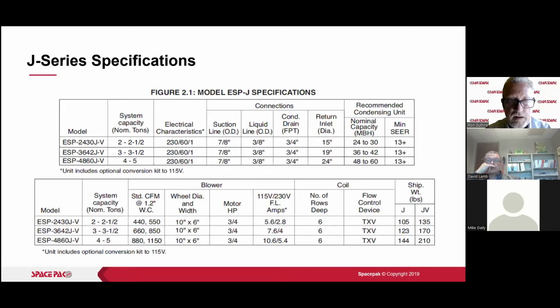And one of the aspects that we need to look at is that if we're doing a commercial job at 208, which is predominantly where you would find 208 volts, the board is looking for 230 volts, and it has some leeway in there. But at 208 volts, it sees that as low voltage, and goofy things start happening with the control of the unit. What we recommend there, if you look under that first chart, is the unit includes an optional conversion kit to 115 volt. If you're doing a commercial 208 volt system, you want to convert to 115 volts and put this in as a 115 volt unit.